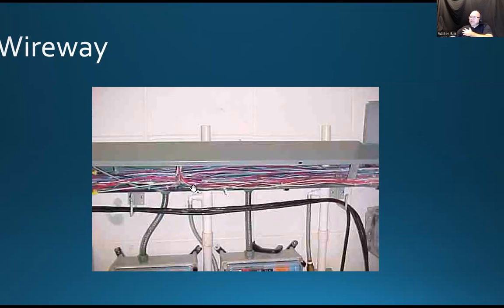So my advice to that is, if you are replacing a system, please make sure you pull your wires out, just so that it can actually be manageable. I have seen those wire trays, especially with the data infrastructure wiring, like Ethernet cabling, that were just filled to the brim, to the point that they were just hanging out of there. You couldn't even close the hinge because of that.